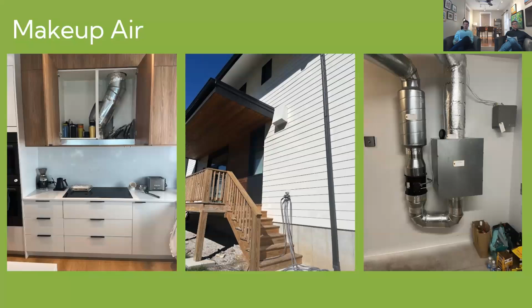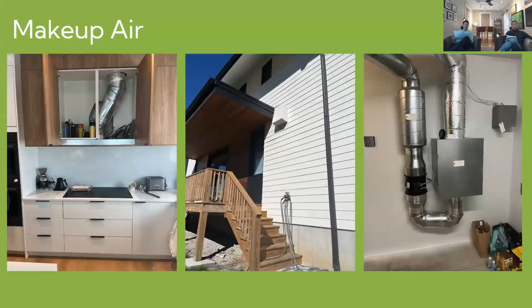One more note on the ERV: if we're moving more than 1200 CFM with a forced air system, this thing's moving 180 to 200 CFM continuously. It's really the respiration system, and everything is optimized to that from design all the way through commissioning. We have a system that does something different than the heating and cooling system, which I think is really important. That's also me commissioning it, so I'm biased.